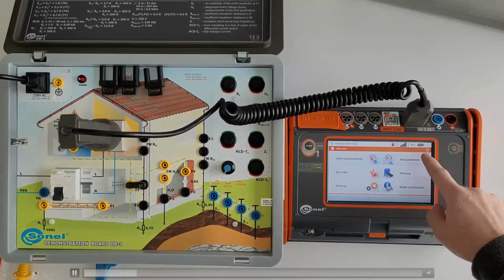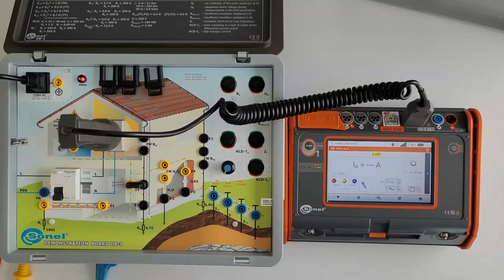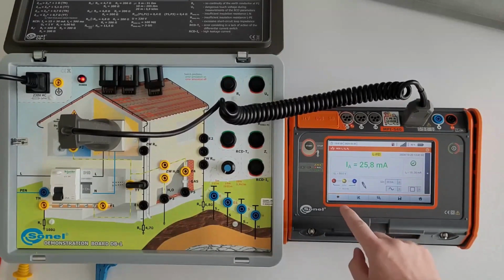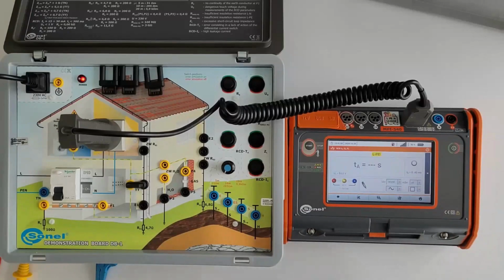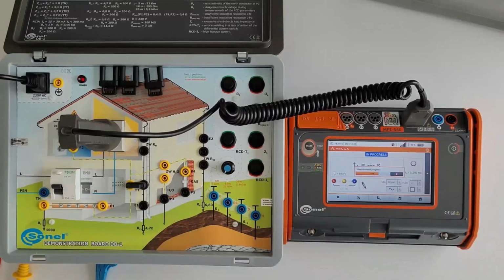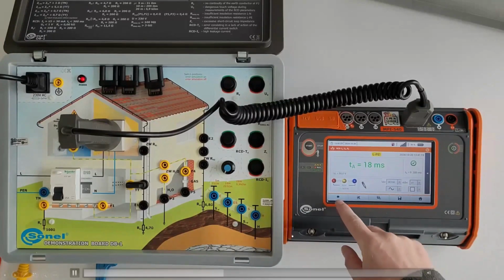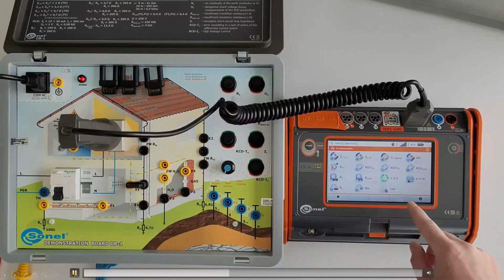How can we do this? Of course, we have to turn on the RCD. The RCD is 30 milliamps, so 25 milliamps is okay. And we measure the trip time for rated current: 18 milliseconds. The standard says that the maximum is 300 milliseconds.